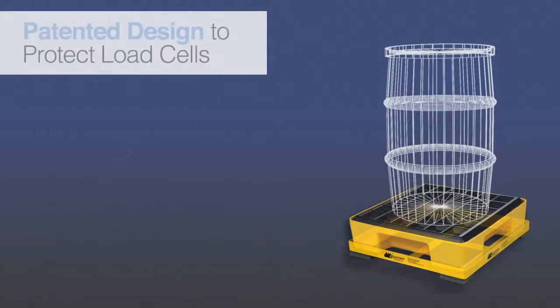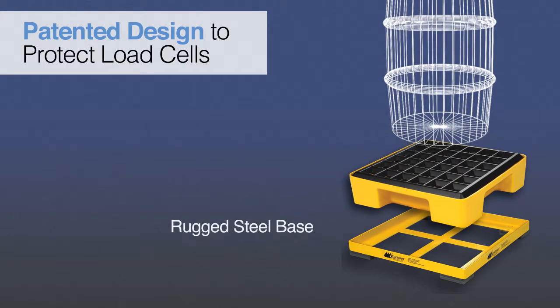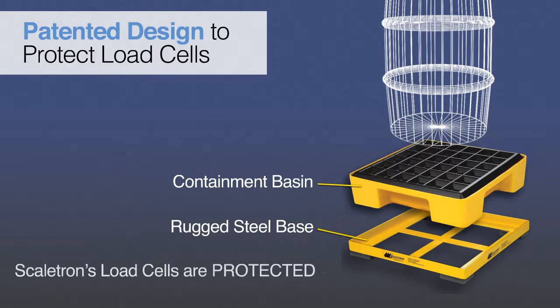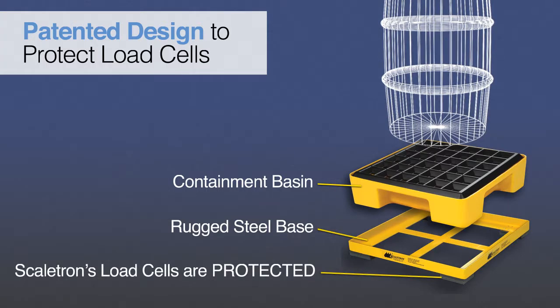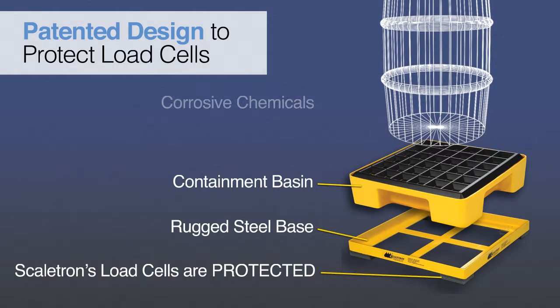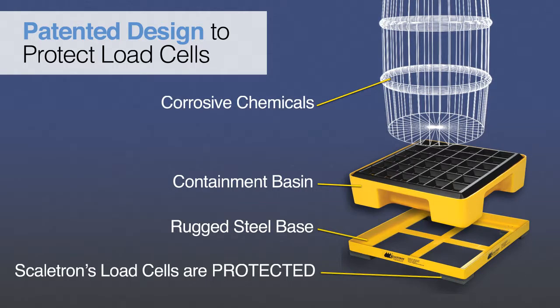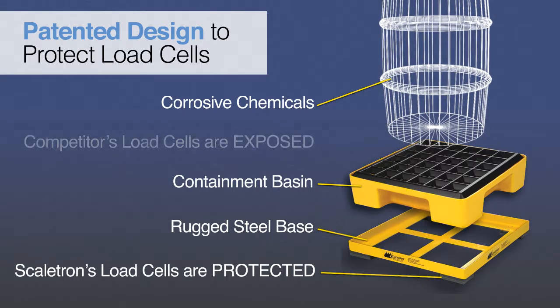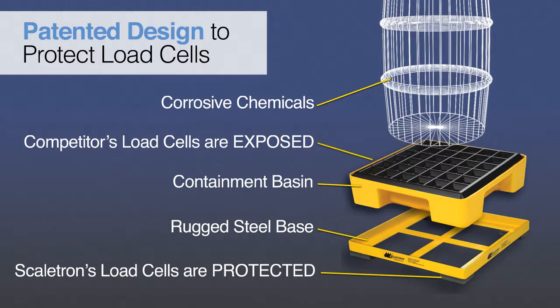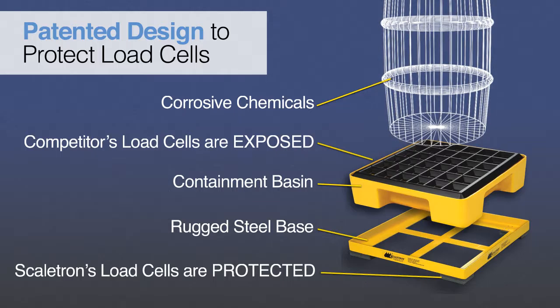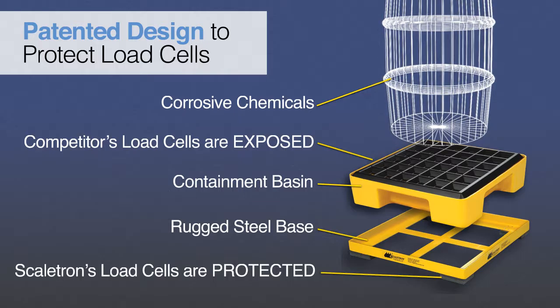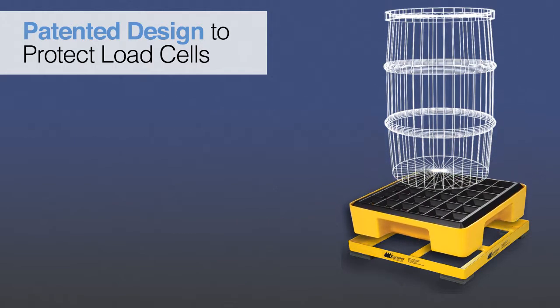Scaletron's patented design features a scale base with a separate molded plastic spill containment basin. The load cells are completely sealed in the scale base, under the containment basin, and out of contact with corrosive chemicals. Other designs on the market have the load cells and wiring mounted inside the spill containment tank, where they are fully exposed to even the slightest spill or splash. Just one spill can cause the load cells and wiring to corrode, requiring expensive maintenance and replacement.